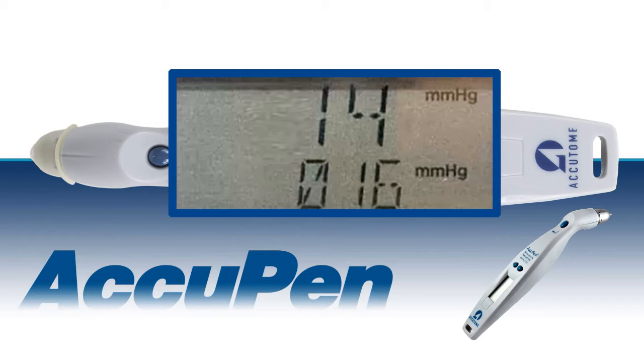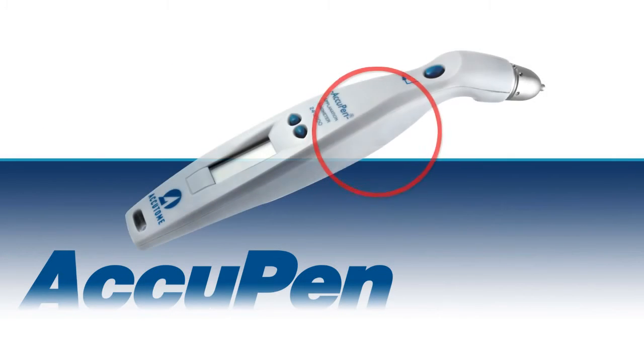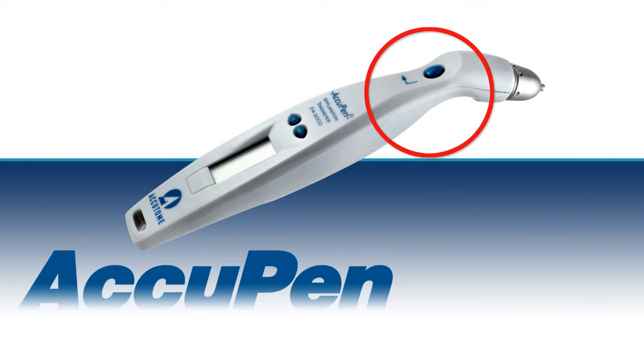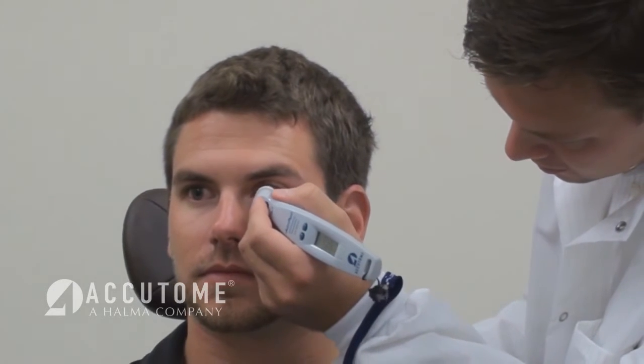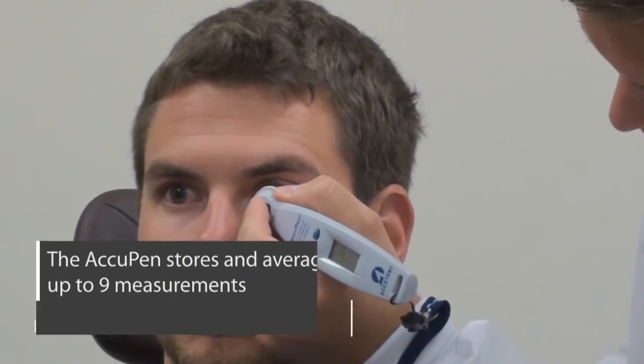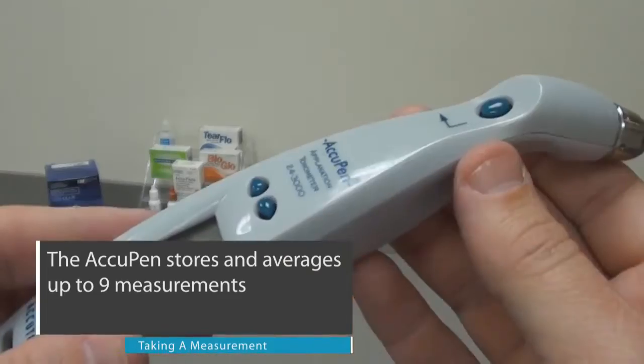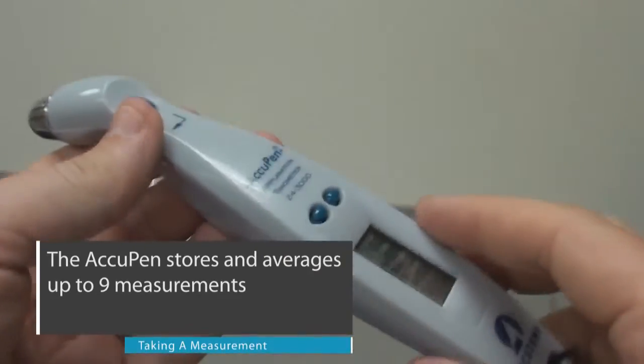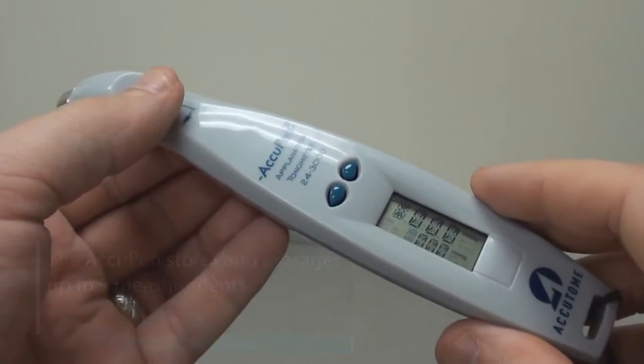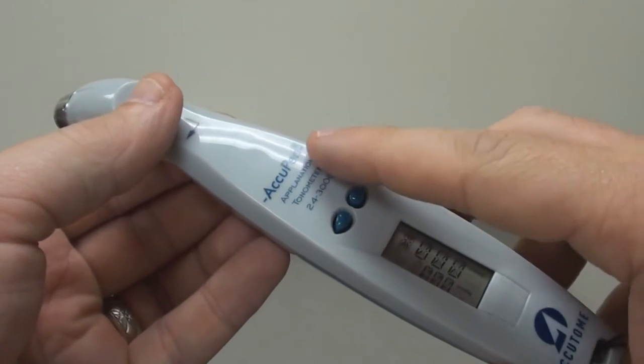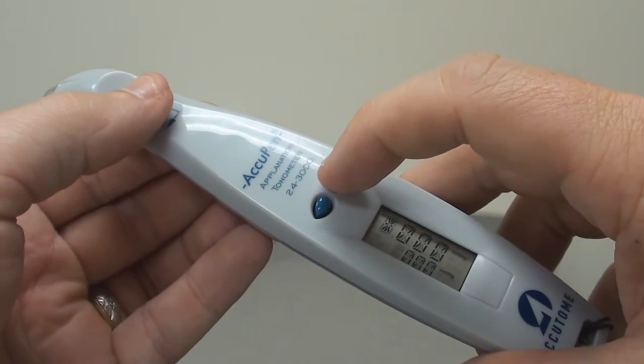To obtain a second IOP measurement, position the pen into testing position. Press and release the action button and tap the cornea again. You can record up to 9 separate IOP readings and can view the independent readings by using the arrow buttons next to the LCD screen to scroll through the measurements. To view the acquired measurements, use the arrow keys.